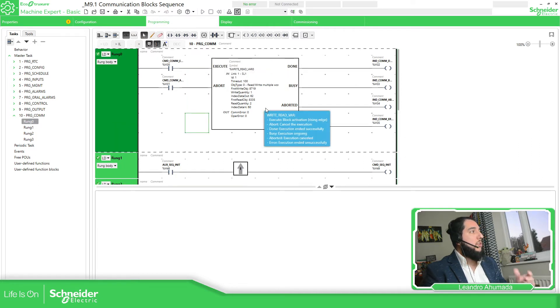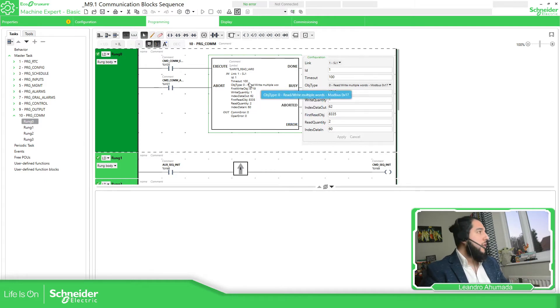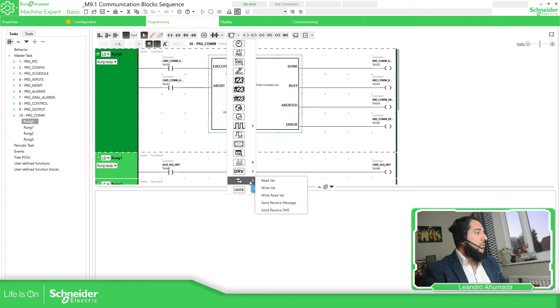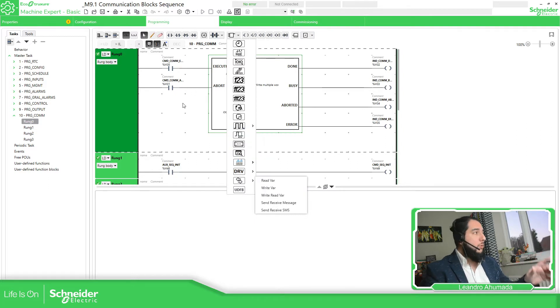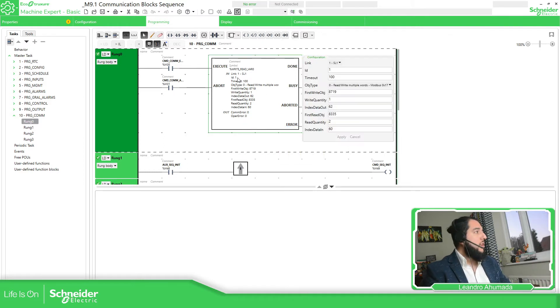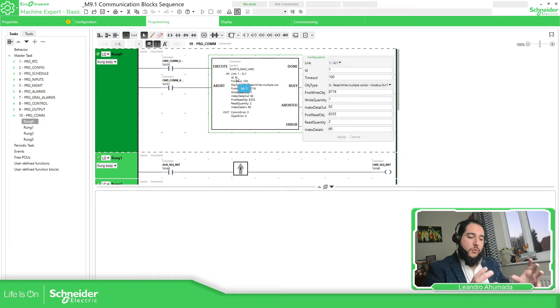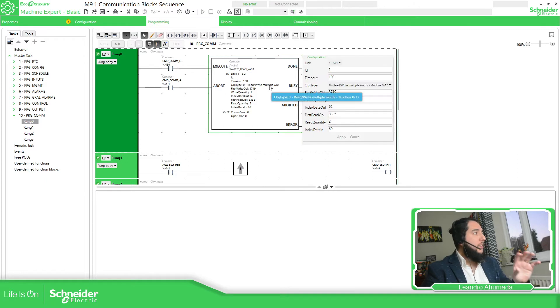In the programming view, you can see the function blocks available for read and write. To add these function blocks, just right-click over the function block you want and place it on the rung. In Modbus serial, the ID is the slave address in the architecture, but in Modbus TCP it's a little different. You will need to create a table, and in that table you have an index to link the function blocks to the communication table you have for Modbus TCP.